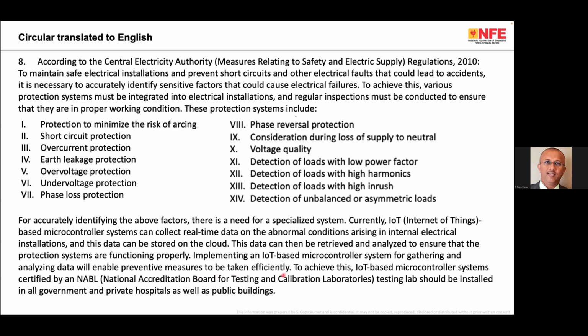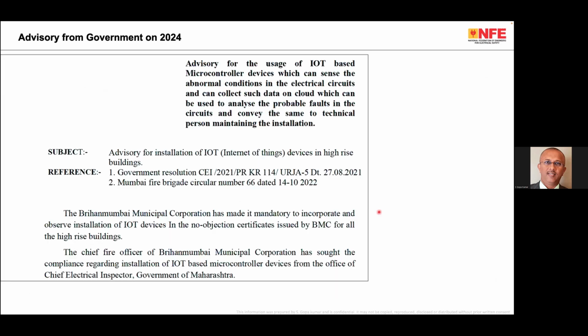So there are a few manufacturers who claim that they make products which are in compliance to IS 732. First of all, this claim itself is wrong because IS 732 is not a product standard. And they say one black box offers all these protective measures. So the energy department made a notice saying that there is an IoT based device, very good, you install. Then the fire department says, okay, based on the energy department, you install it everywhere. Then later the energy department says that every electrical inspector should ensure that this device is installed in all the high-rise buildings.